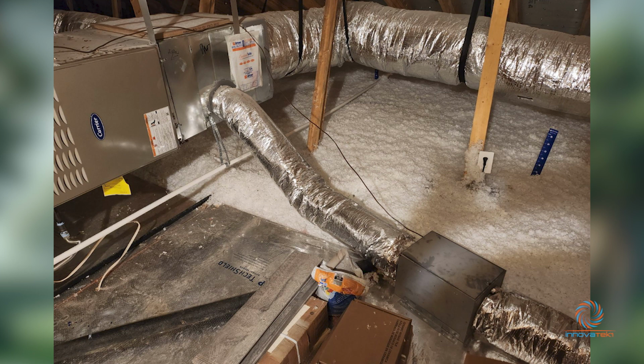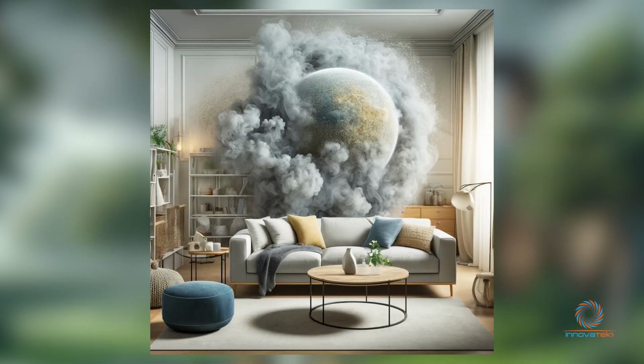A lot of the time, these new houses are so tight that you rarely open a window or door to bring in fresh air. So the air inside your home, if you don't open windows and doors sometimes, can be up to 5 times more polluted than the air outside without you even knowing. So by code, they require new construction homes to provide a fresh air ventilation system. The problem is that a lot of the time this device is not configured correctly by the technicians.